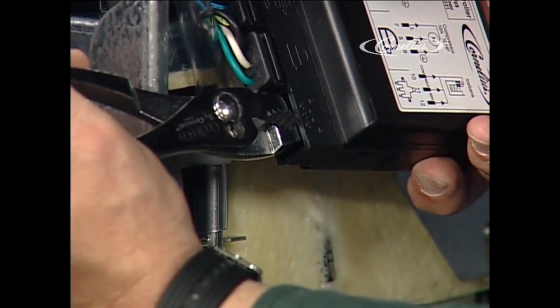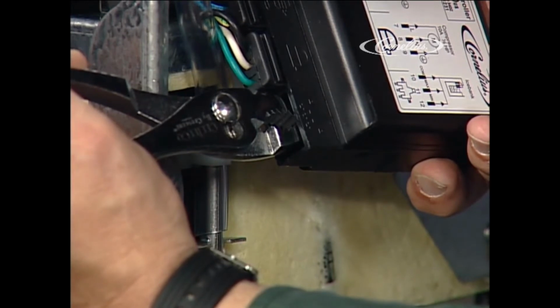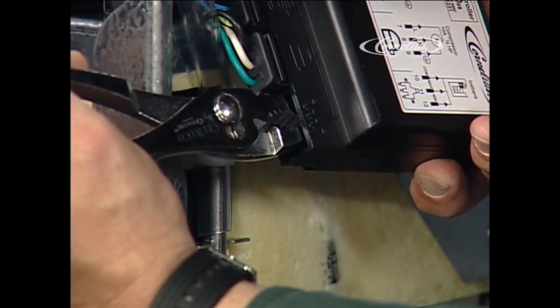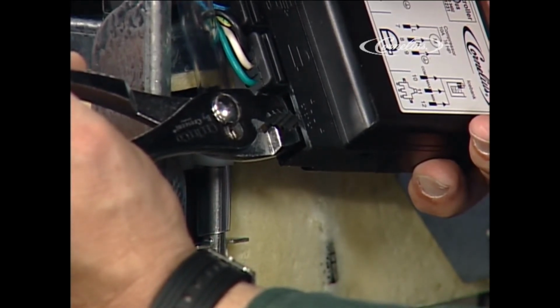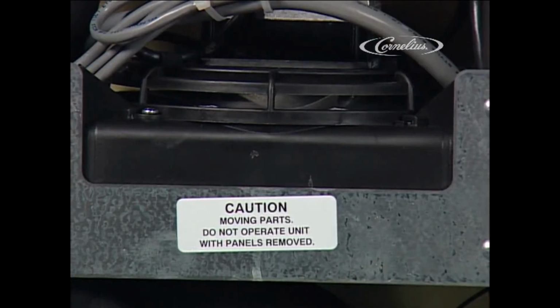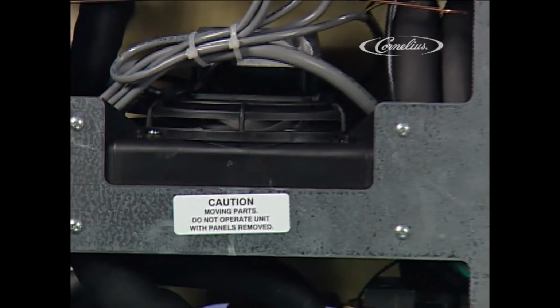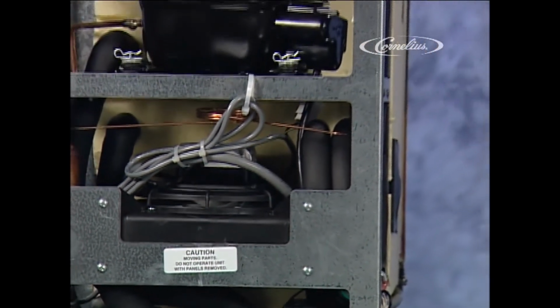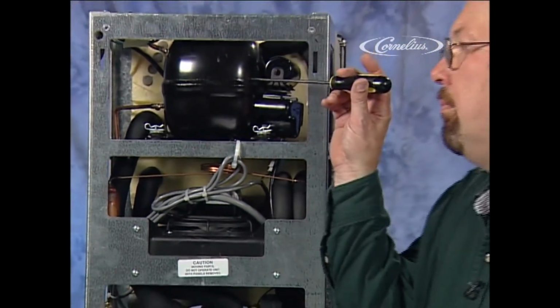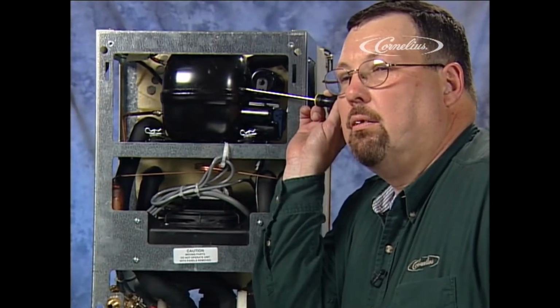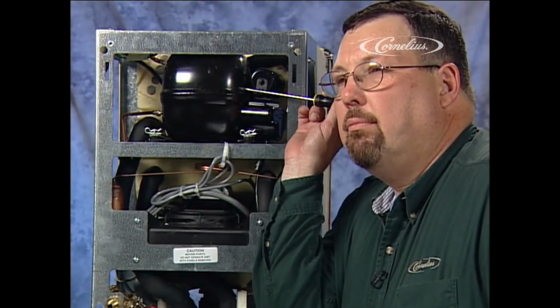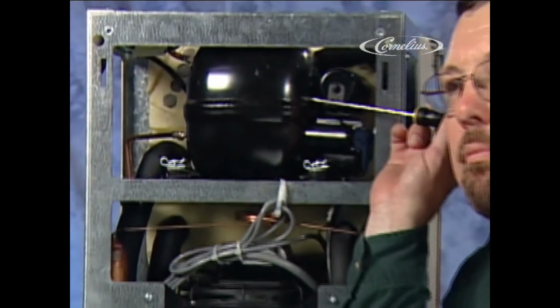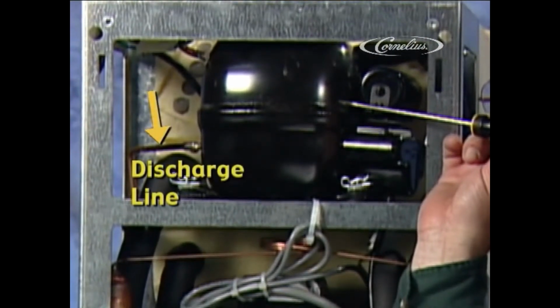The condenser fan and compressor are wired in series. If voltage is getting to it, then unless there is a break in a wire or a problem with the electrical components of the compressor itself, the compressor should be operating. Be advised that this compressor runs very quietly. It may be necessary to place the blade of a screwdriver against the shell while placing your ear on the handle. This, plus the heat on the discharge line and shell, will tell you the compressor is running.